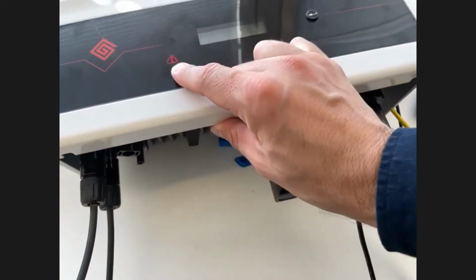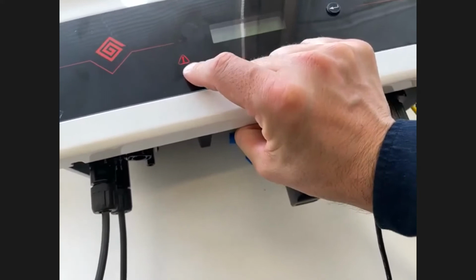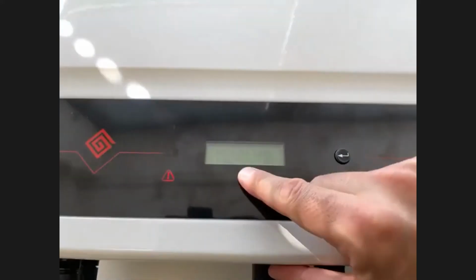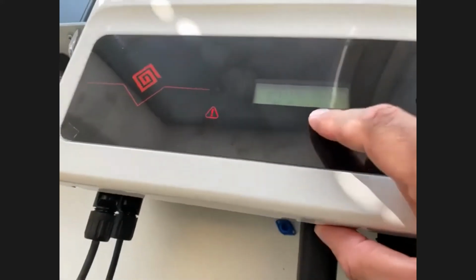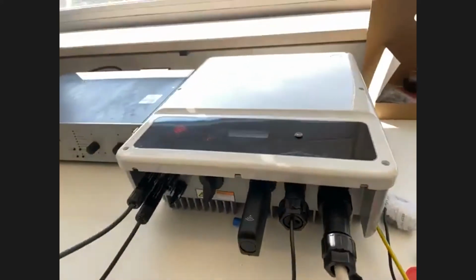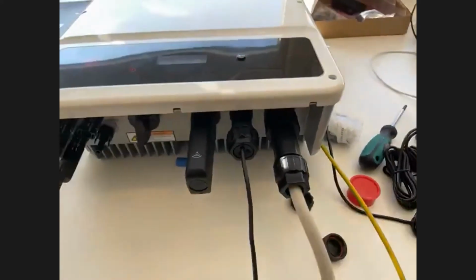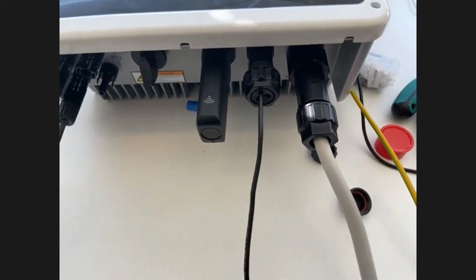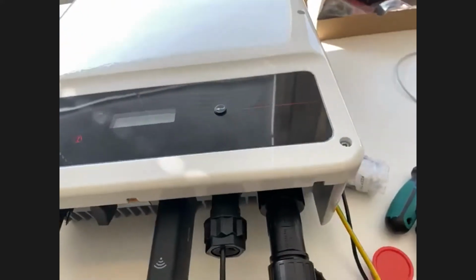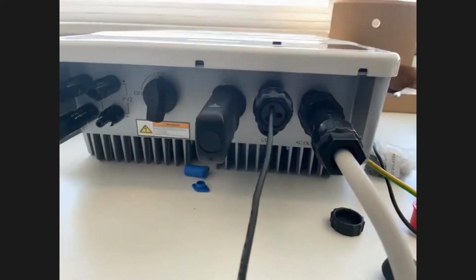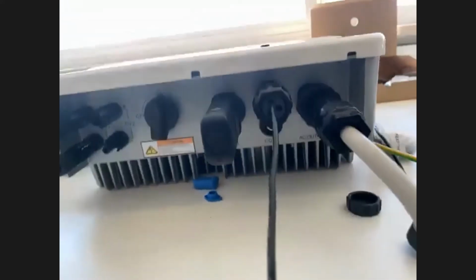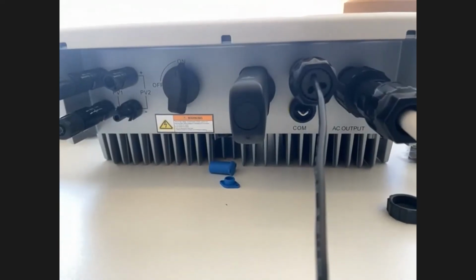This one is also shining red. That means that there's an error. And if you look on the screen, you can actually see that it says utility loss. And that means that the inverter is not connected to the AC line, which is true in this case. This is not connected to anything. So it's exactly as it should be right now. Okay, so now I will leave the camera here, and then I will go through how to commission the inverter. And then after that, we will look at how to add it into SAMS.